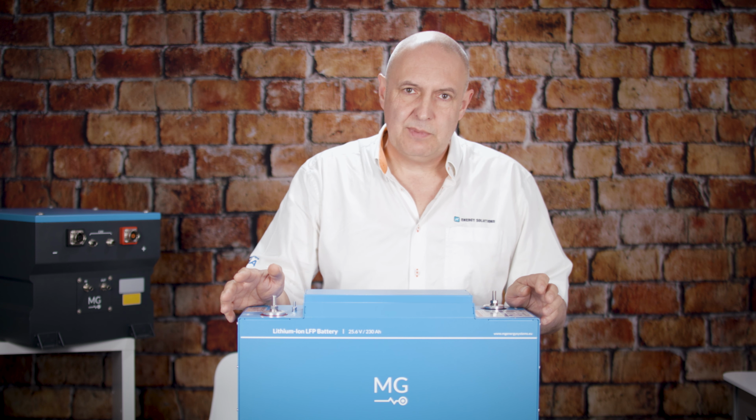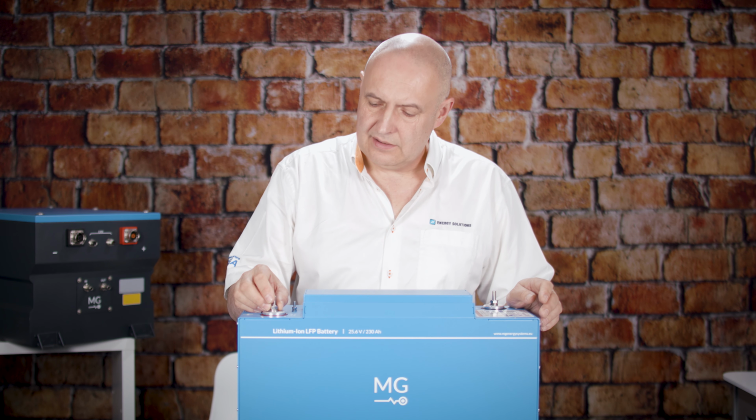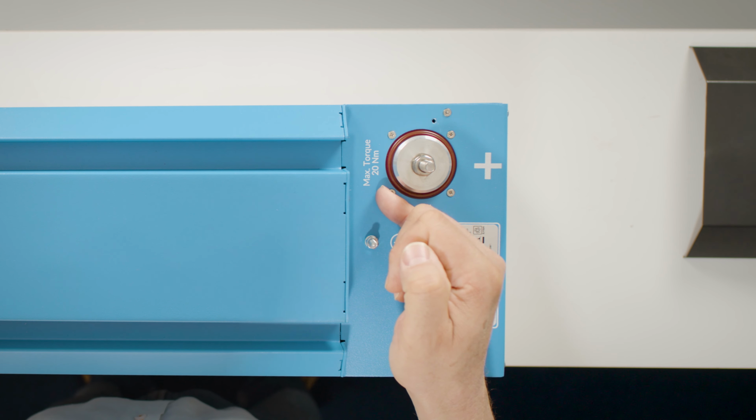When installing these batteries, it's very important that you torque the studs on these battery terminals to the correct level. It is actually printed on the top of the battery that you need to apply a maximum torque of 20 Newton meters.